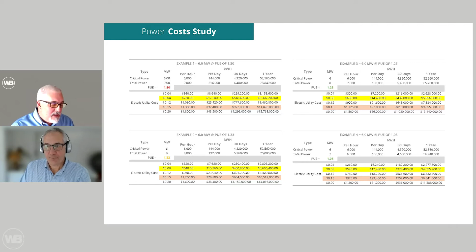Yeah, sorry. So PUE is power utilization effectiveness, basically. What it does is take your critical power and your total power for your facility, and you divide your total power by your critical power. So in this first example, we have 6 megawatts of critical power, and we need 9 megawatts to run the facility, which means all of your ancillary equipment, your HVAC and all that. When you take 9 divided by 6, you get 1.5.